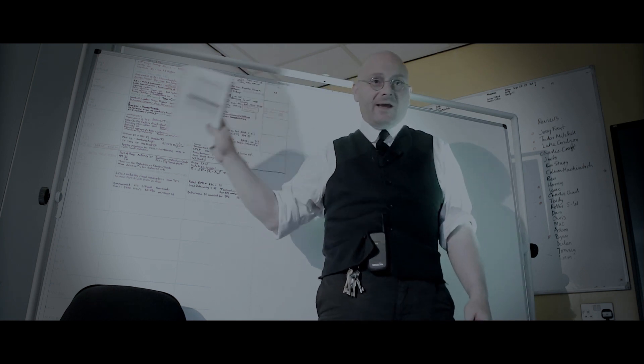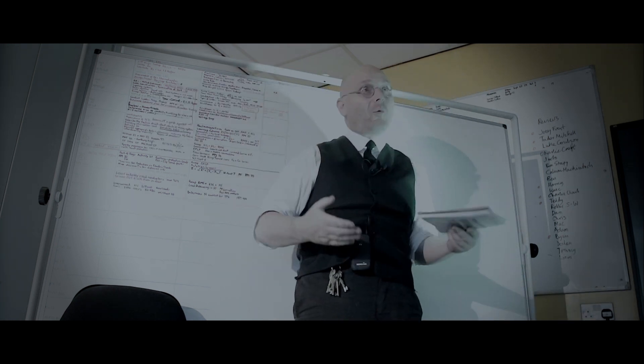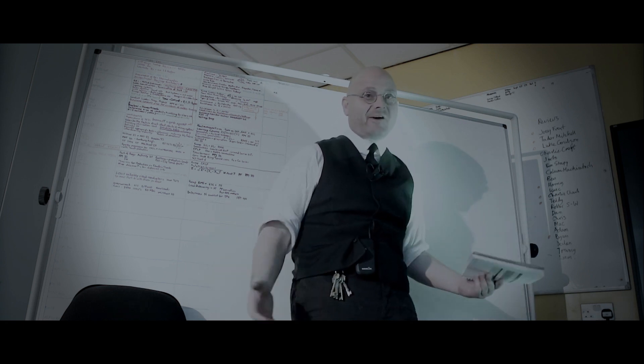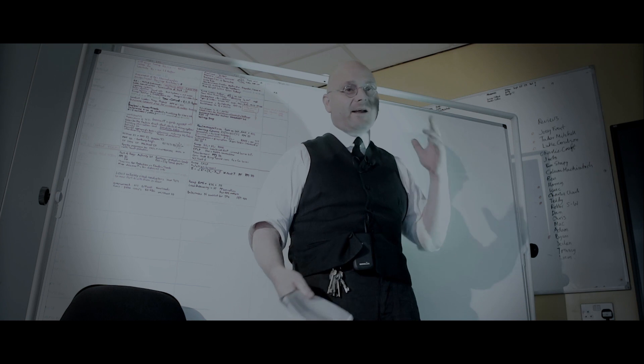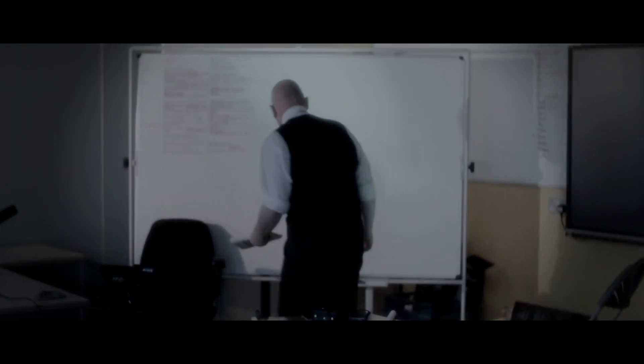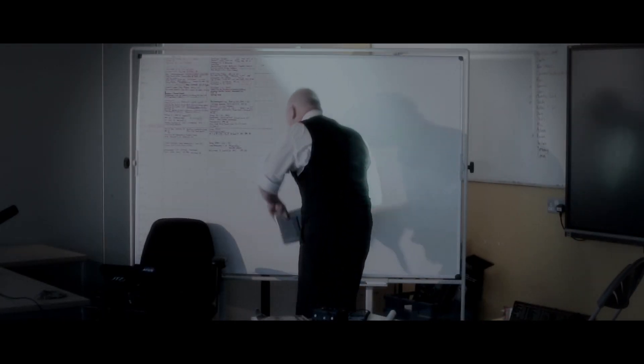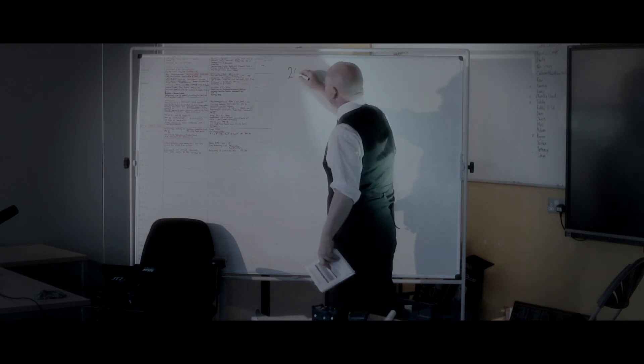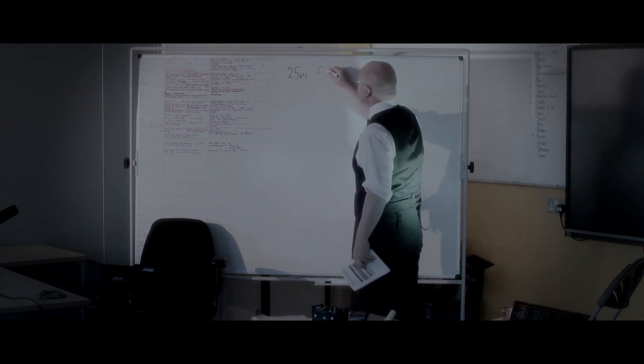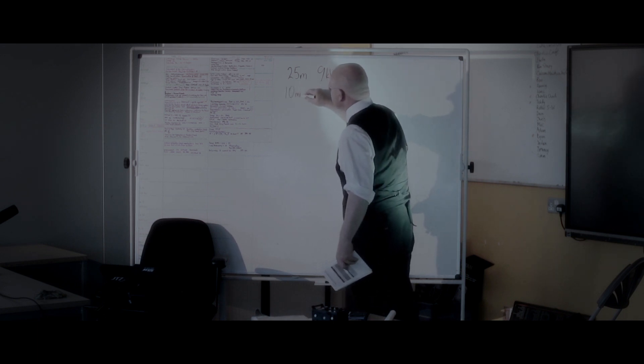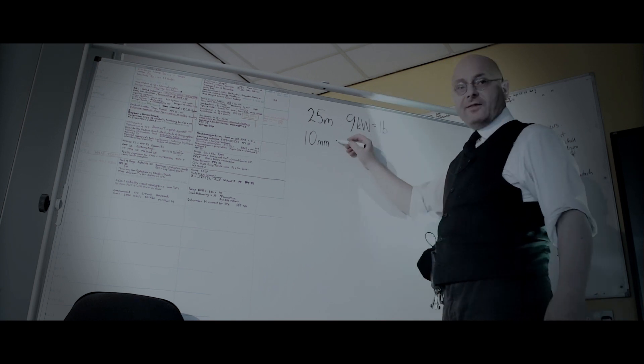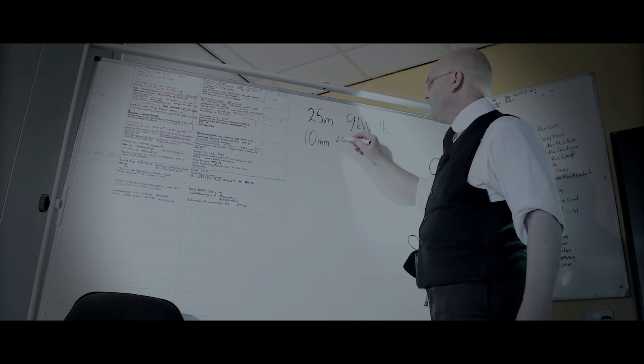The way we do it is by working out, first of all, what the fault current is going to be in our designed circuit. So let's go back to that 9 kilowatt, 25 meter circuit. 9 kilowatts equals IB. We used 10 millimeter twin and earth with a 4 millimeter CPC.